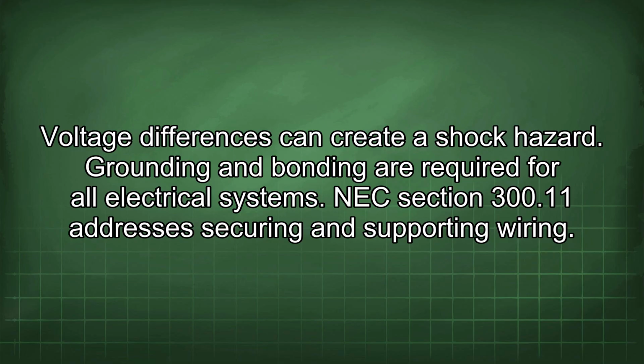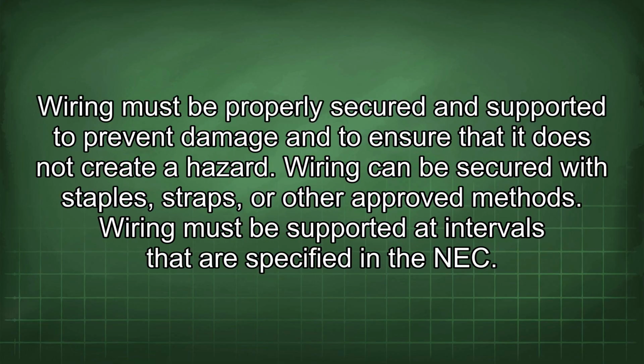NEC Section 300.11 addresses securing and supporting wiring. Wiring must be properly secured and supported to prevent damage and to ensure that it does not create a hazard. Wiring can be secured with staples, straps, or other approved methods. Wiring must be supported at intervals that are specified in the NEC.